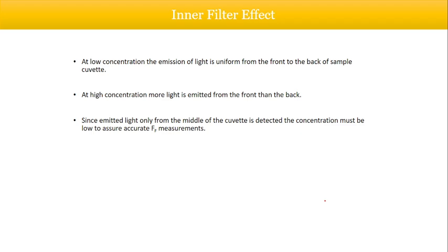But this filter is because of the intrinsic property of your sample. So on increasing the concentration, it actually acts as a filter. This is called the inner filter effect. Since the emitted light from the middle of the cuvette is detected, the concentration must be low to assure accurate measurements. At low concentration, it is not much of a problem, because the light can penetrate and give accurate results.